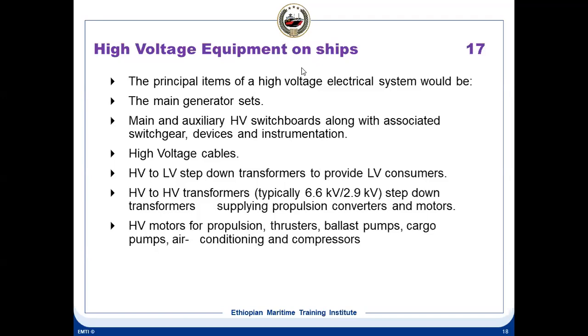High voltage cables. These high voltage cables you will normally find on board ship. The color is not like normal cables which you see on 440 volt ships, where black cables are used. Here it's a different color, pink, so that you can identify which is a high voltage cable and which is a normal cable. No other cable is supposed to pass nearby this high voltage cable, because of the harmonics and electromagnetic interference. No instrumentation cables or other cables should pass near the high voltage cables.